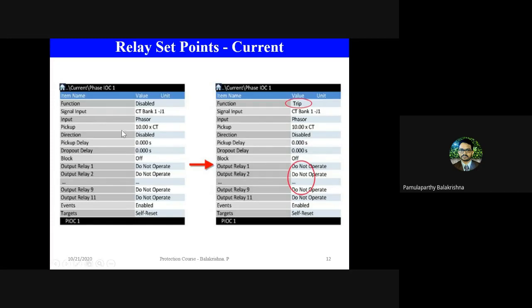There is also something called dropout delay. How this dropout delay works is, you see a current greater than 10 times the CT ratio, and you configured the pickup delay as 50 milliseconds. Once the current level crosses this 10 times CT, it will wait for 50 milliseconds. But within that 50 milliseconds, if the signal falls back to less than this level, it will again wait for the signal dropout time before declaring not to trip the breaker. Which means once it has picked up and there is a timer running, if by any chance the signal drops out, it will wait this much time to see whether the signal stays dropped for that particular amount of time, so that it will not execute any control action. But if the signal goes back to the normal level, the pickup timer picks up again and then trips the breaker.